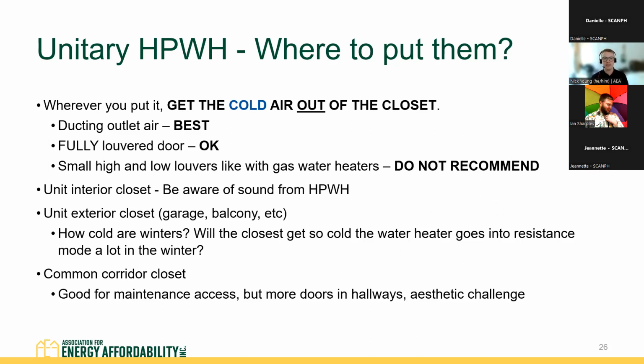So the best way is to duct it out. You could also have a fully louvered door. So we're talking about the whole door being louvers, top to bottom. You will see manufacturers tell you that small louvers, high and low, like we're used to doing with gas water heaters, a little louver up here, a little louver down there, are okay. I do not recommend it. We do not recommend it to anyone. They will tell you you can do it. I do not recommend it. Fully louvered door or duct the cold air out. That is my recommendation.